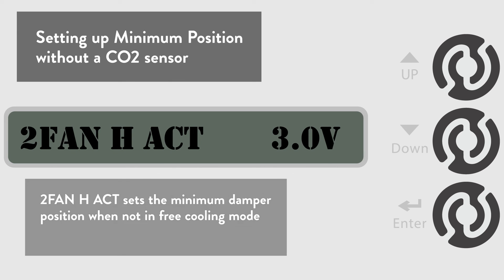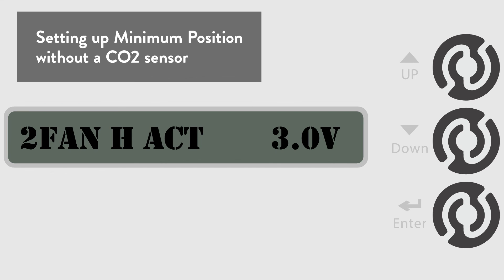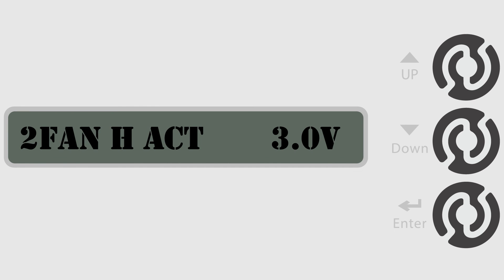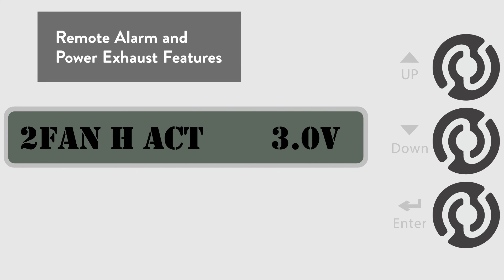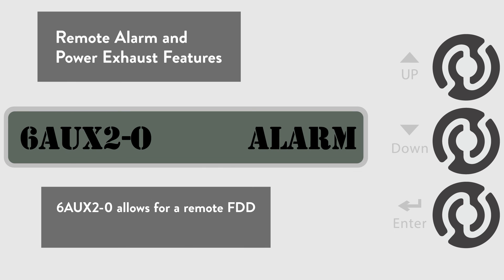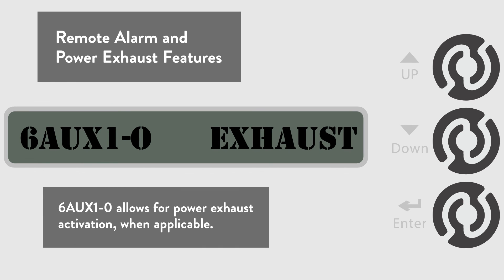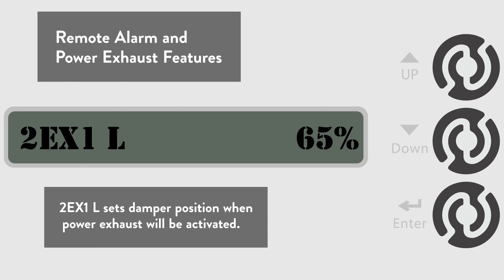The last two items we are going to discuss are for informational purposes: the settings for power exhaust activation and alarms for fault detection. Even if you do not use these features, you can leave the settings at the default. Scroll down to the 6-AUX2-0 menu. The default is set to alarm to allow a signal to be sent to a remote light or thermostat signifying that a fault has been detected on the economizer. The remote alarm feature is required by many building codes, including California's Title 24. Our last example will be the 6-AUX1-0 menu. The default is set for exhaust for use with a power exhaust. To change the activation setpoint, go to the 2-EX1-L menu, where the default is set for the power exhaust to kick on when the outside air damper is open to 65%. But for this example, we are going to change it to 75%.